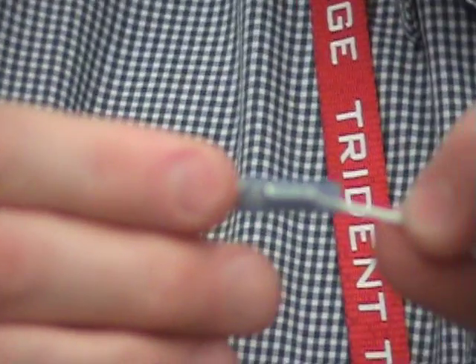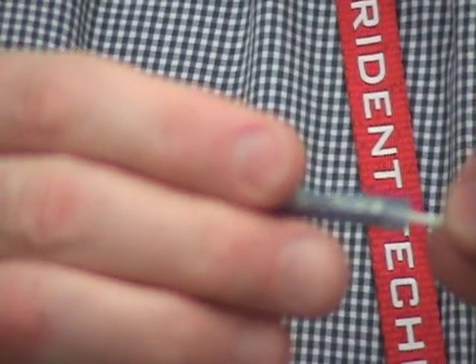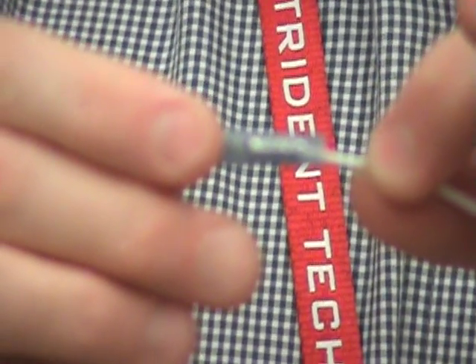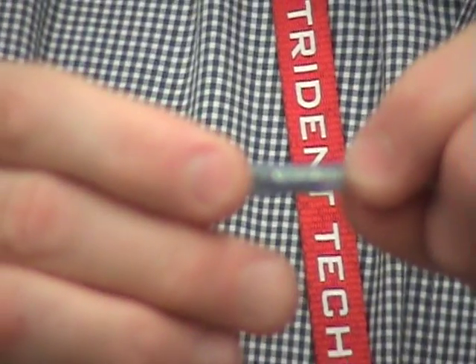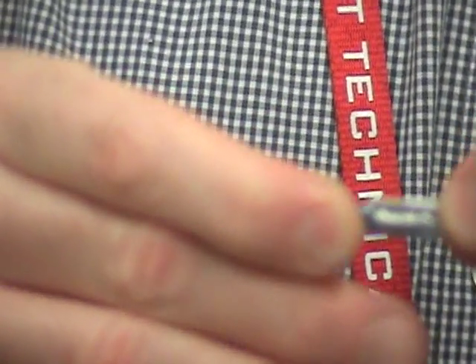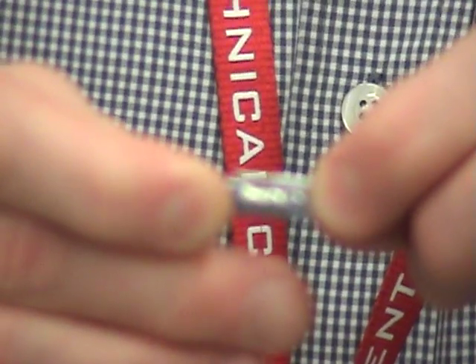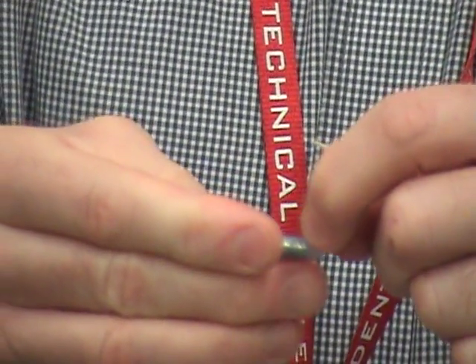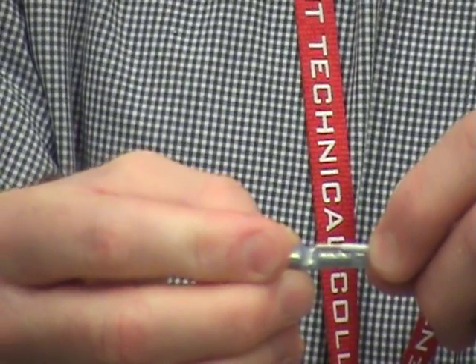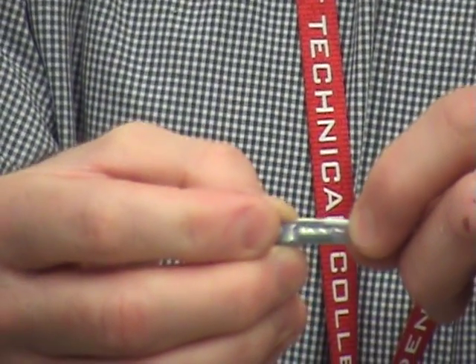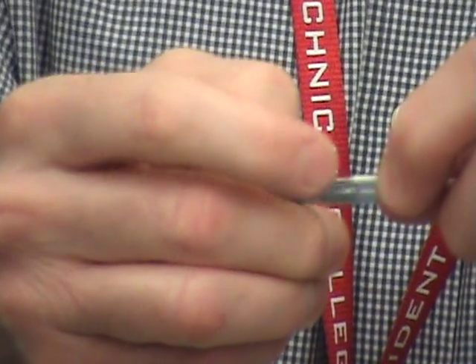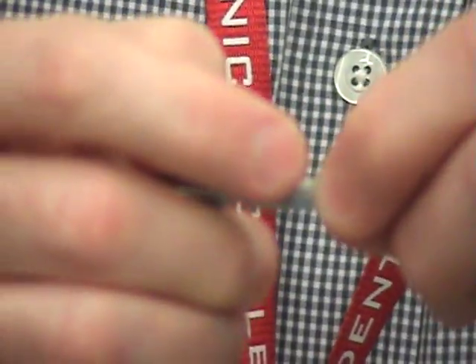Remember the wire needs to go into the splice and be seen in the window. I'm going to put it in here, it's going to be seen in the window, but yet my wire length, it's going to hit the window, but there's a little line where the insulation is going to hit the line and yet there's still a little bit of metal here that's going to crimp on the insulation itself. So these crimpers have two crimping points. One on the tinned wire and number two on the insulation.